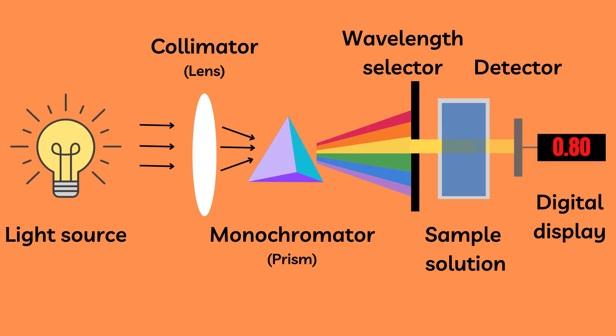So next, let us take a look at the different components that make up the device. Here we first find a light source, then a lens called the collimator which focuses the light into a prism or grating known as the monochromator. This in turn splits the incident beam into different wavelengths, and by using an adjustable slit called a wavelength selector, a suitable wavelength spectrum can be selected.